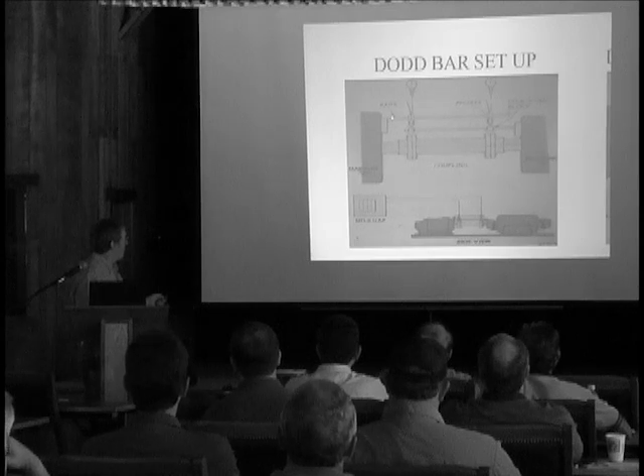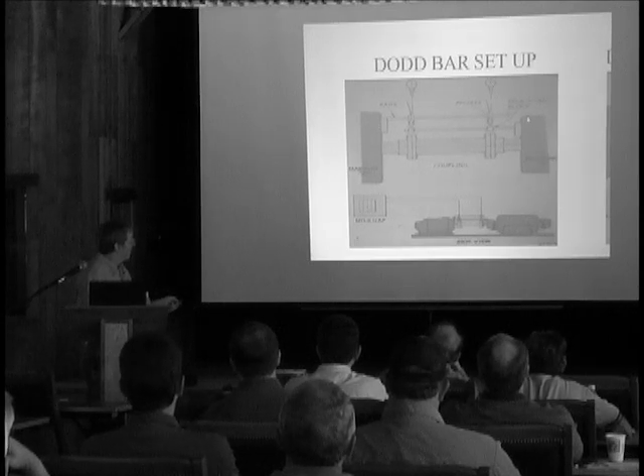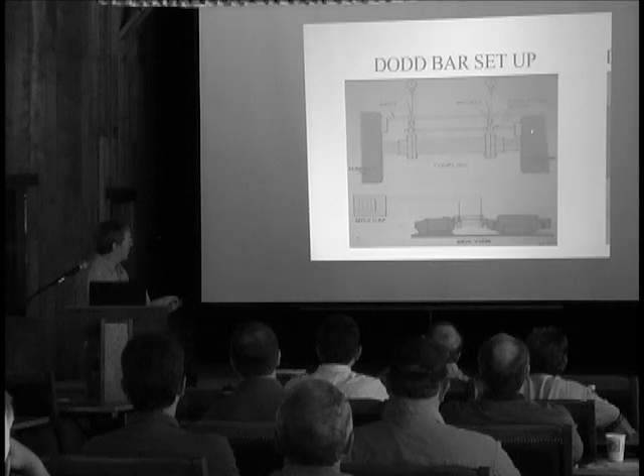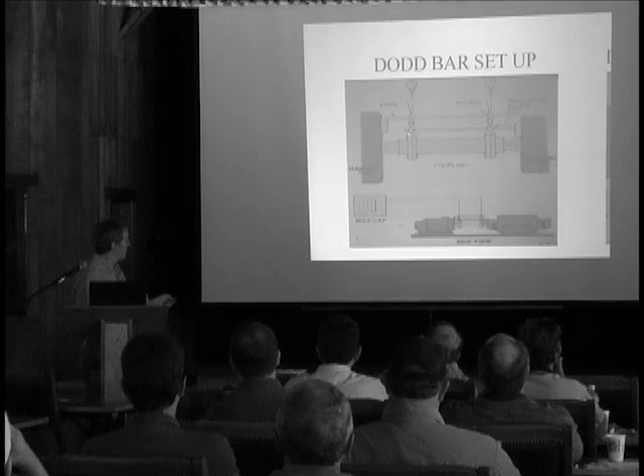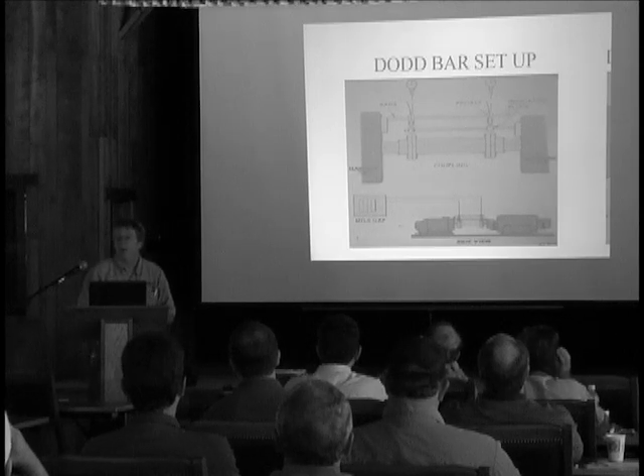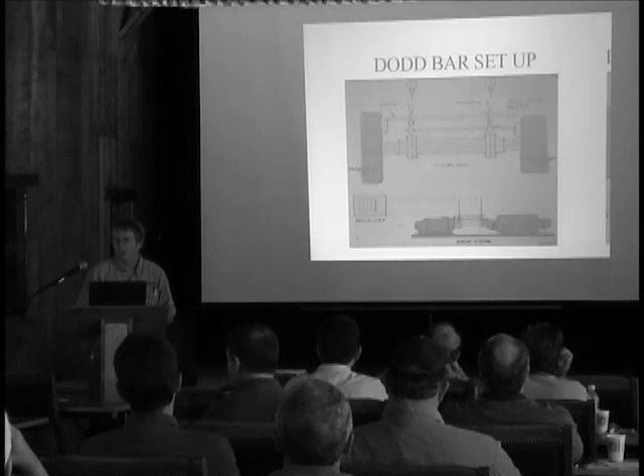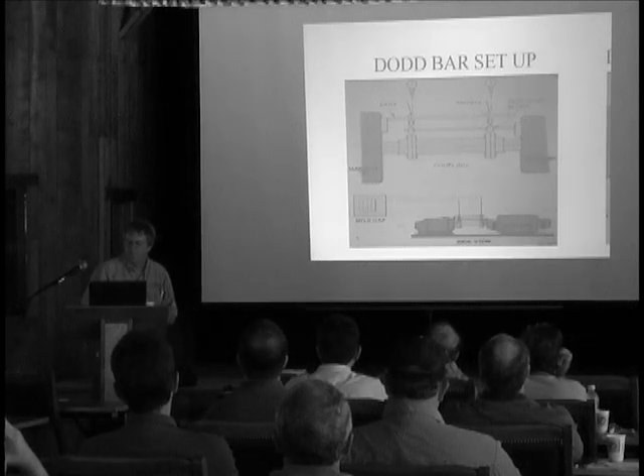You mount a set of bars from this machine. You mount a set, and they have proximity probes, vertical and you can't see them, horizontal. You mount a set of bars on this machine with a set of targets, and then you bring the machine up. If there's any vertical change, the gap closes or opens, and the same thing horizontal, and you monitor alignment online real time. And this was like 25 years ago.